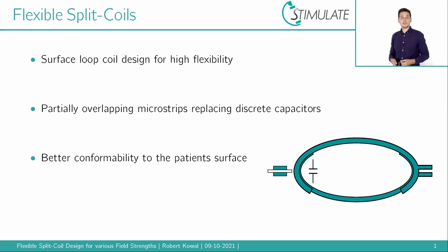By this, we no longer have any rigid solder joints on the coil and thus can achieve a higher conformability on the patient surface. We have no longer the risk of failure by breaking, may have possibly increased image quality and an easier handling.